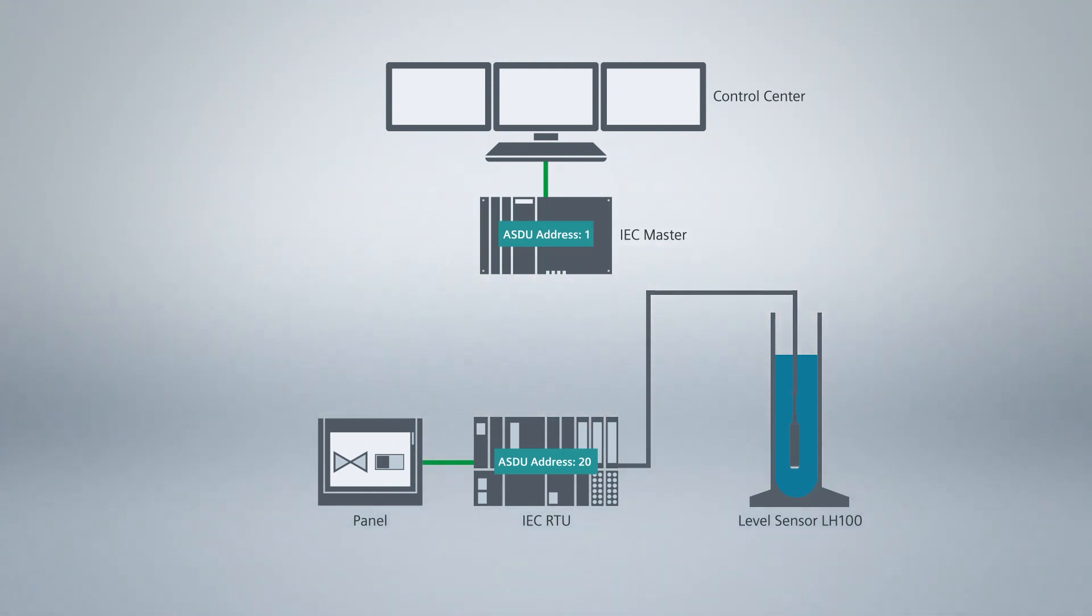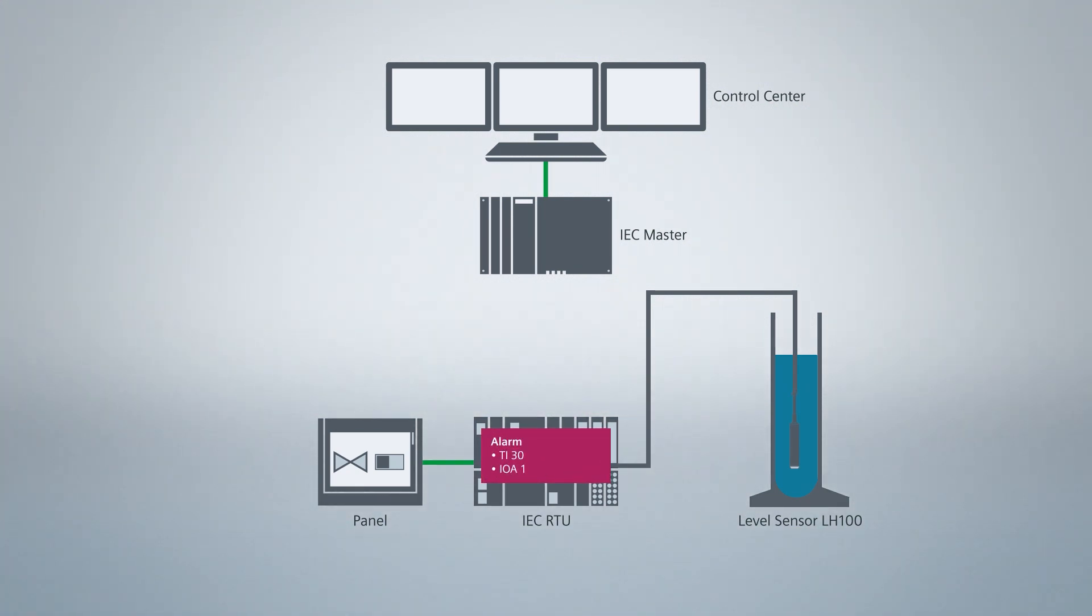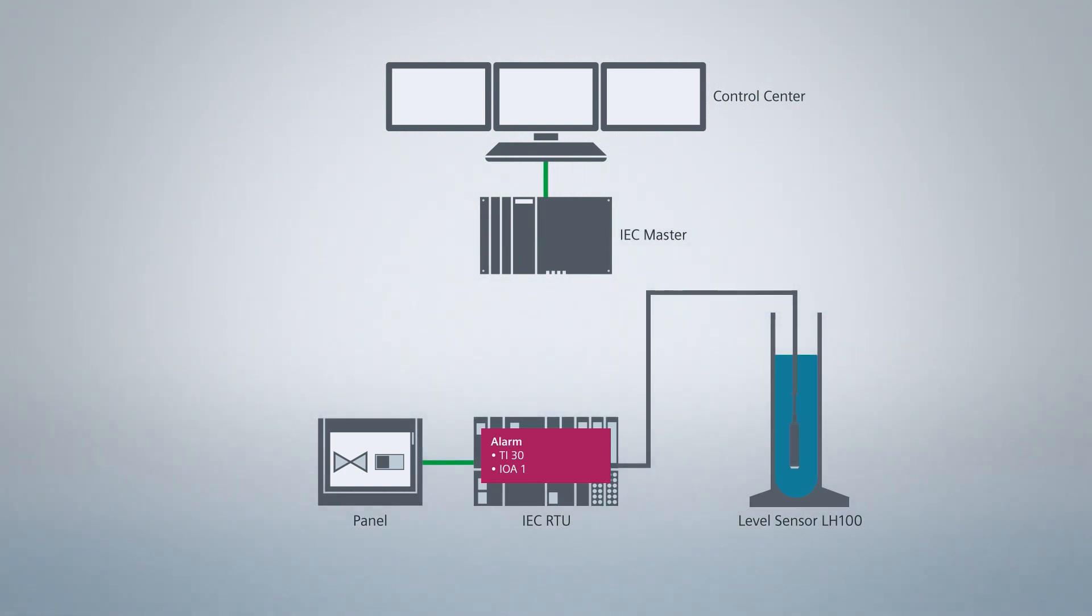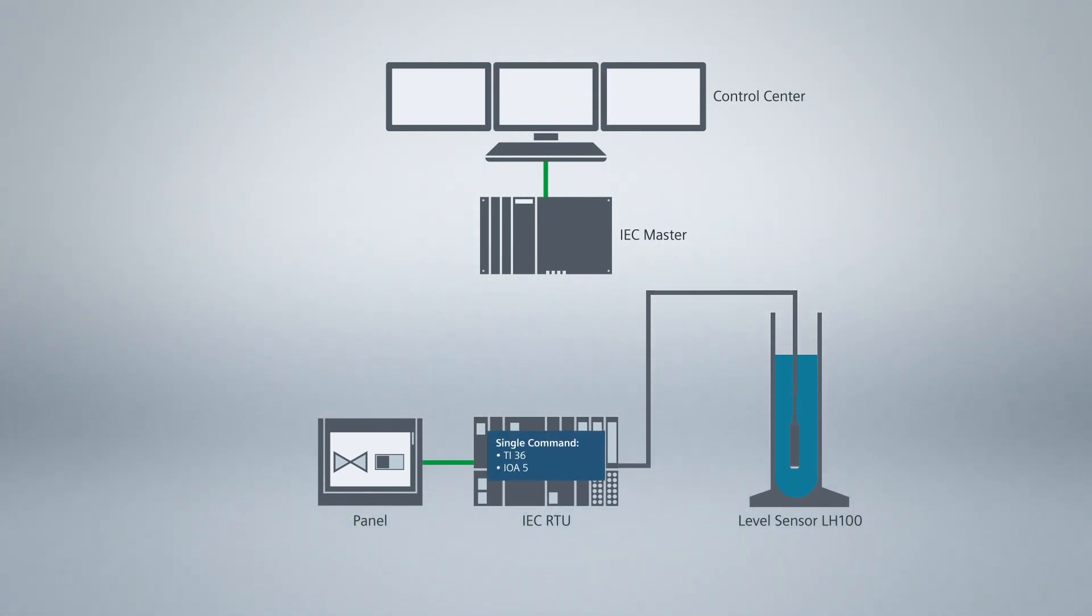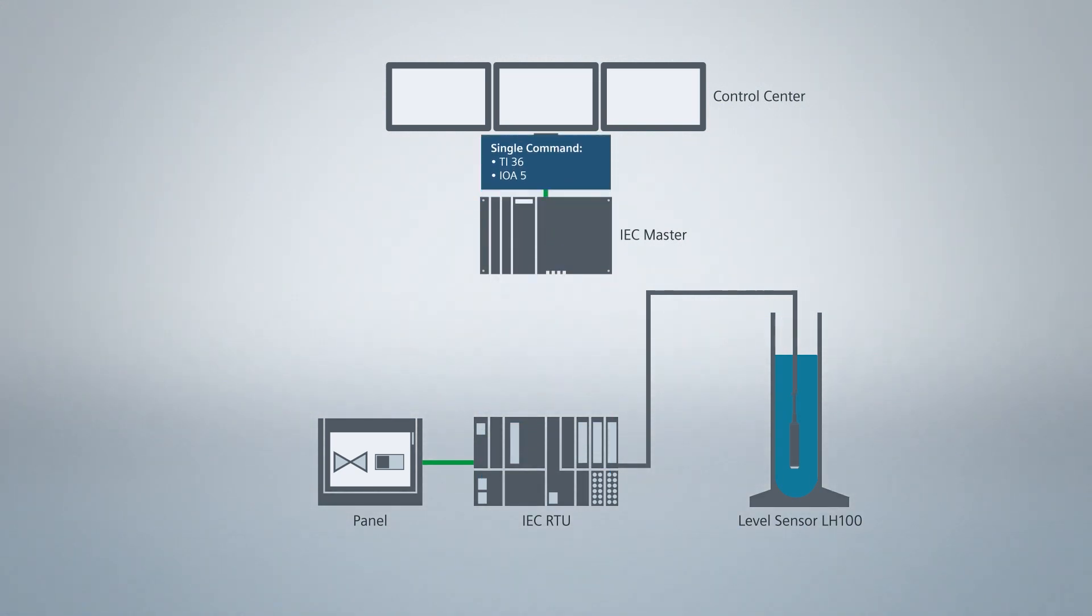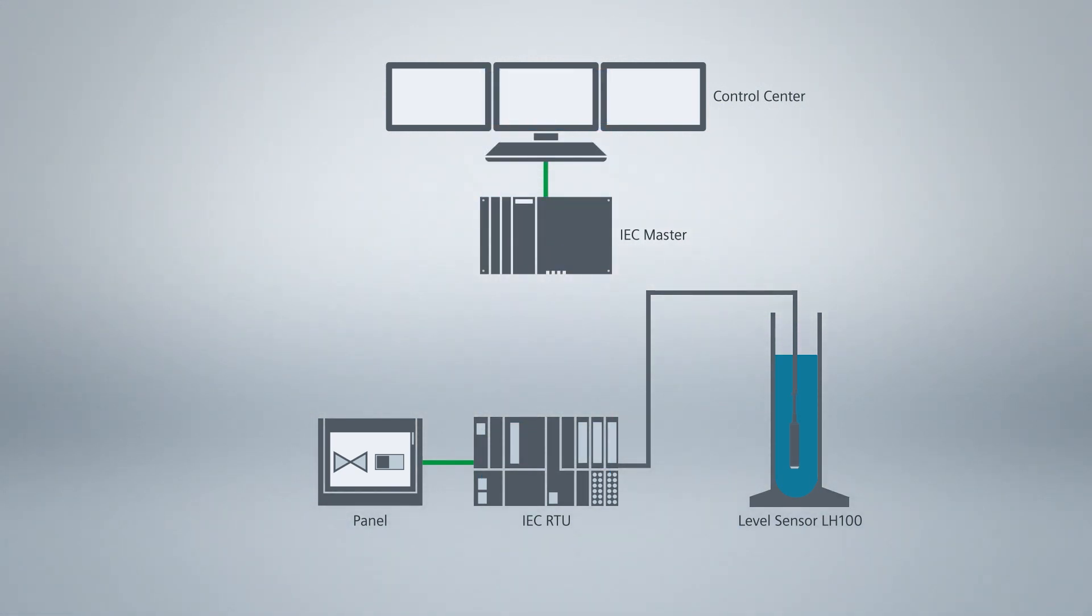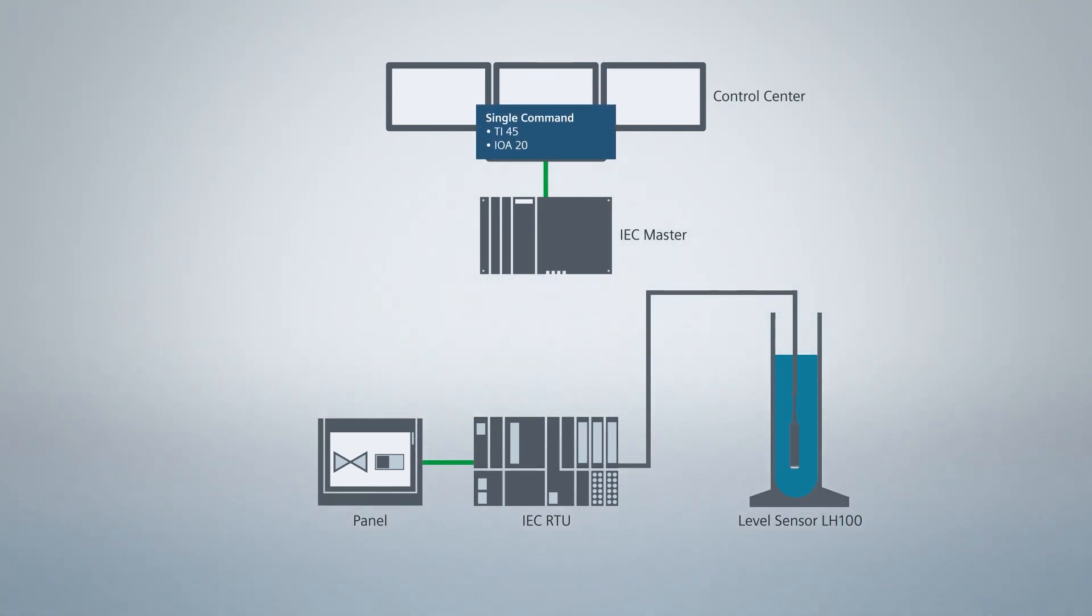Our IEC RTU is to transmit an alarm and a measured value to the control center. The alarm is a message with timestamp, thus a single point, TI-30. The information object address, IOA for short, is 1. The measured value is a real value with timestamp. According to IEC standard TI-36, IOA address 5. The command from the master to the RTU is a single command. According to IEC standard, TI-45 with IOA address 20.